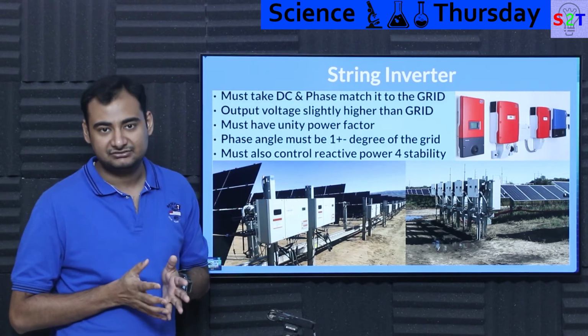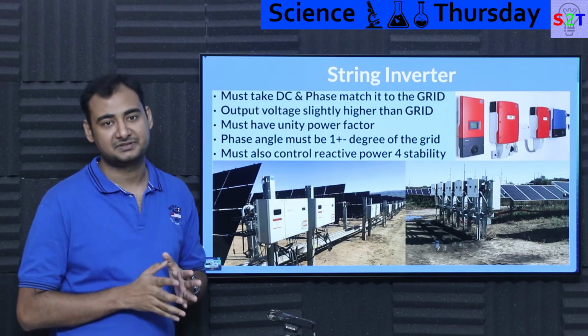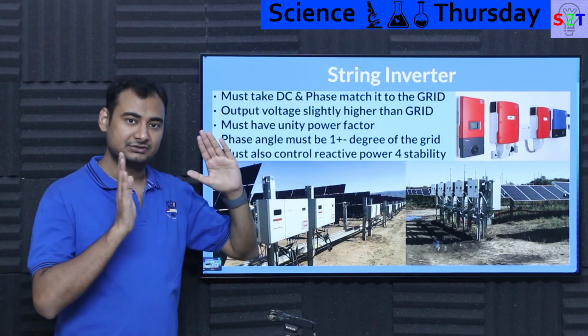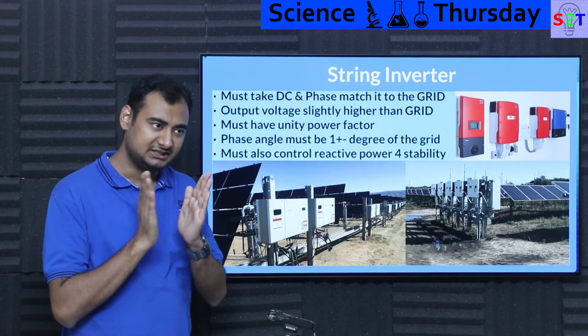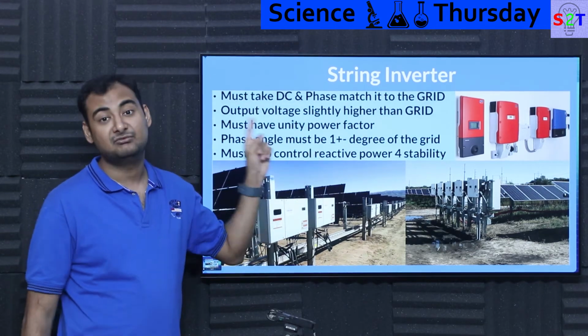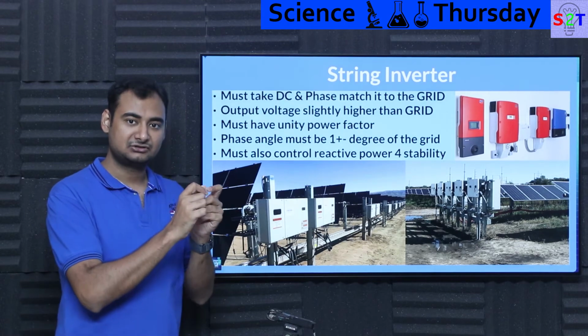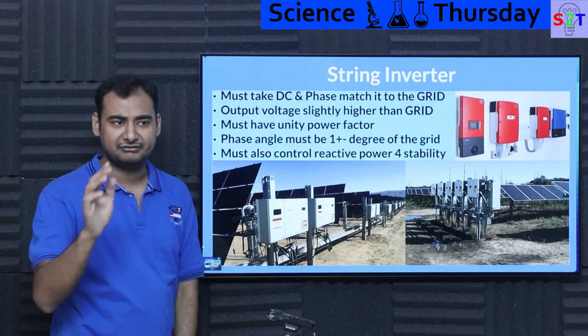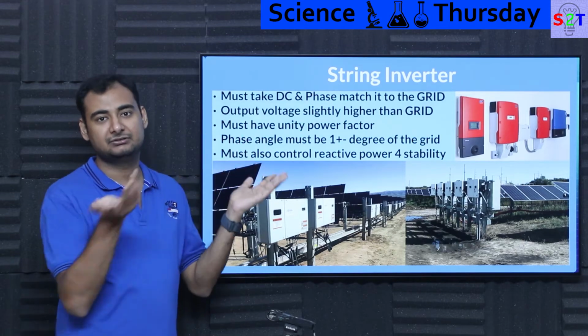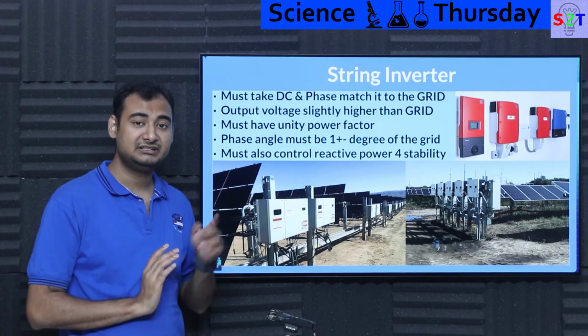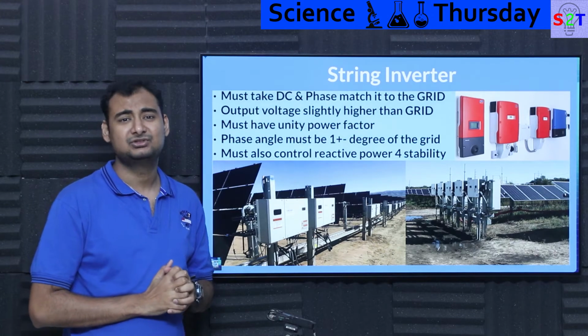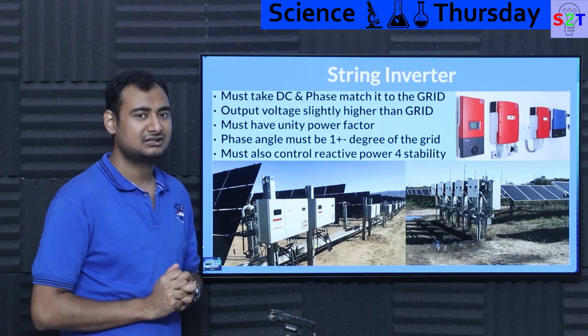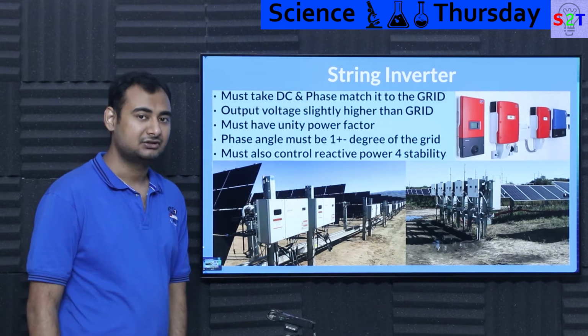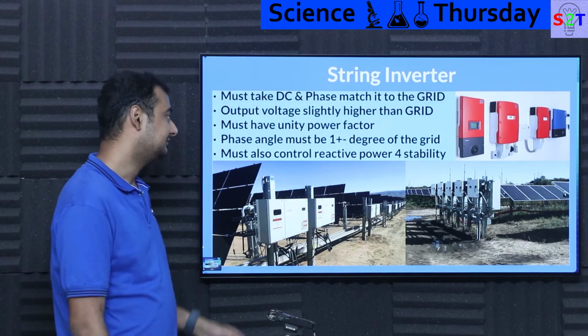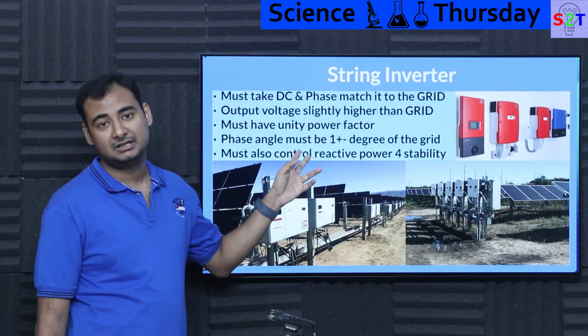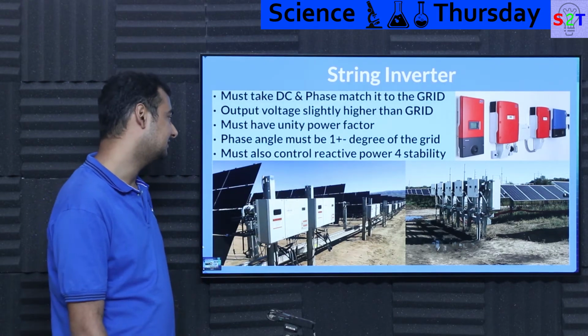And because of the reality of the situation, you never have a scenario where anything is 100% perfect. So even if you are looking at the phases, there is a maximum allowable tolerance, basically you must be within 1 degree of separation. So if you run it through an oscilloscope, you should be good enough. It should not be like, hey dude, it's starting to drift, your transformer is gonna go boom if that happens. So fundamentally 1 degree is allowable. If you're talking about a loose regulation, you can get away with 2, but the moment you start to reach 3 or 4 degrees, your inverter will overheat, and after a while it's gonna catch on fire. So it must have phase angle matching to around 1 degree plus or minus.